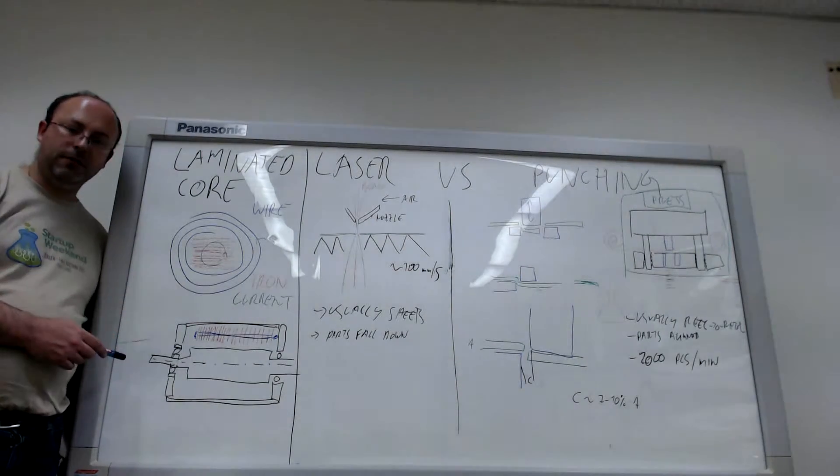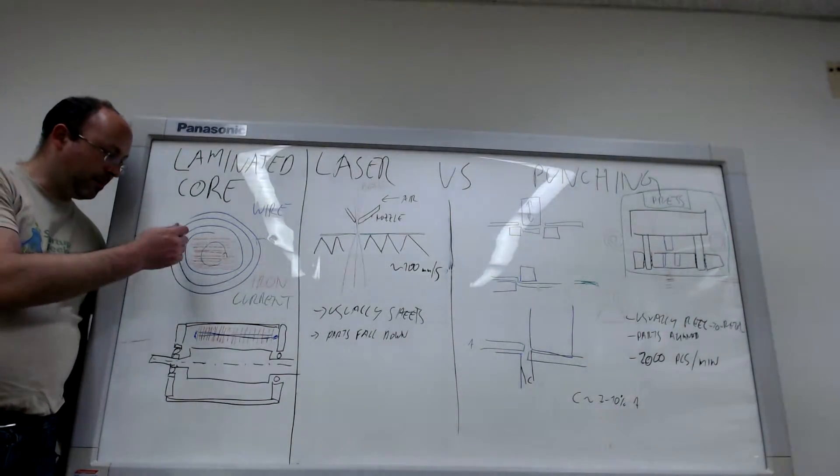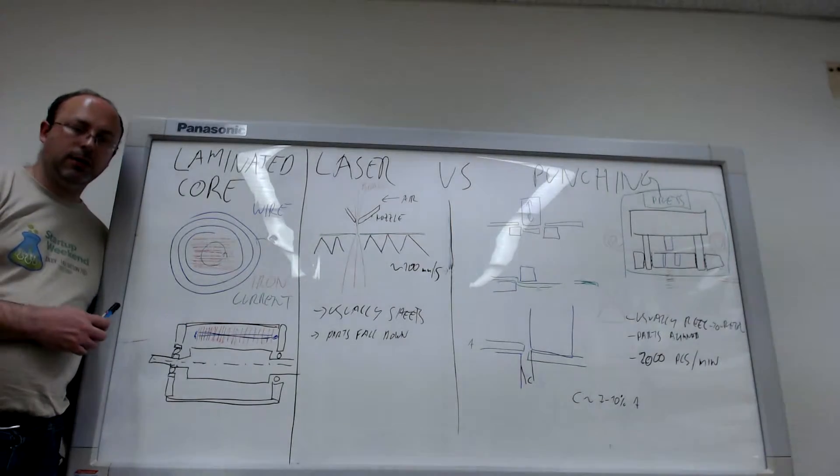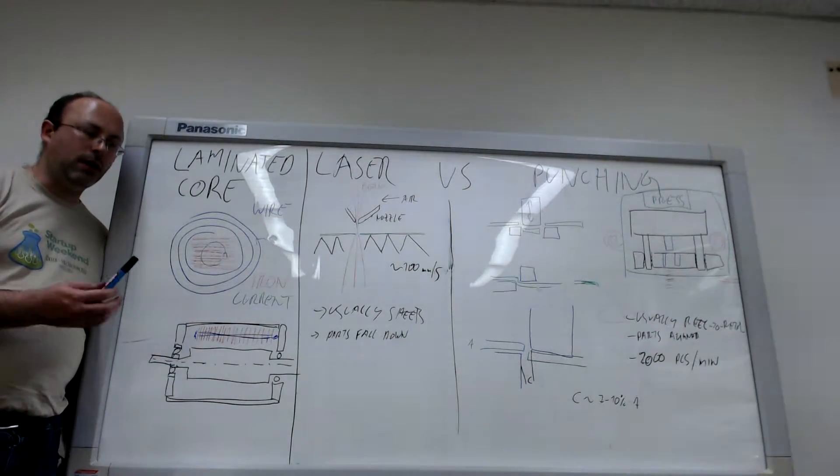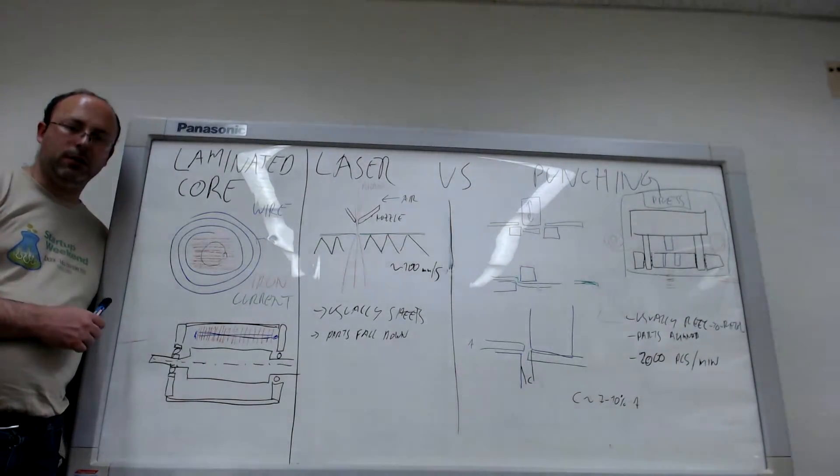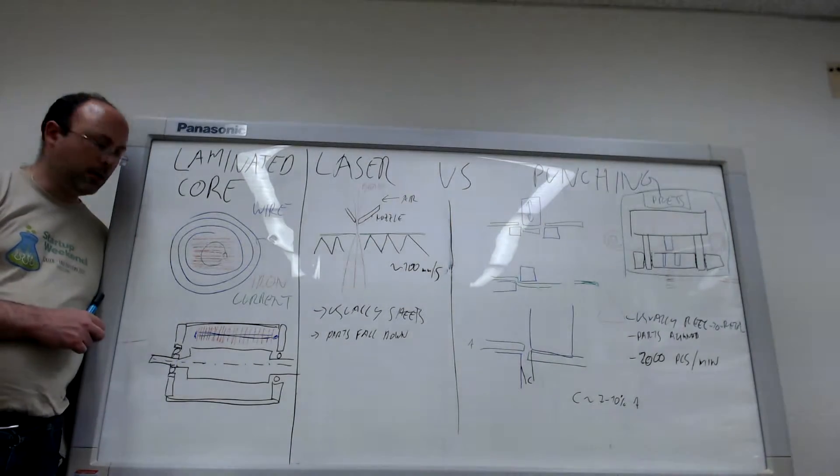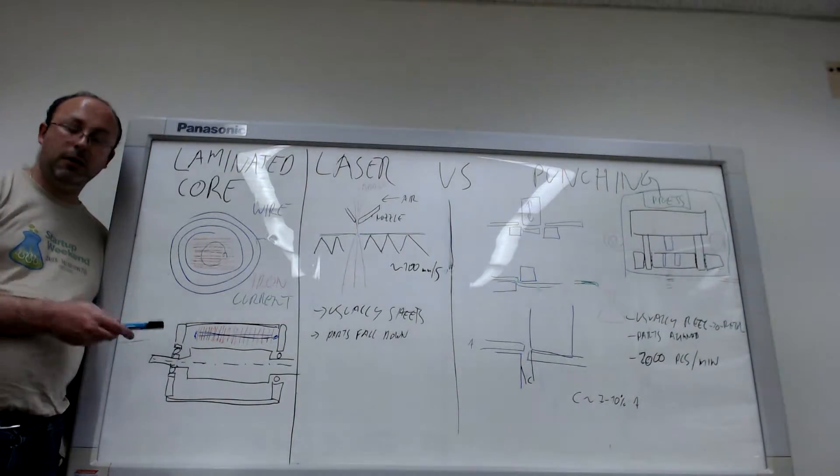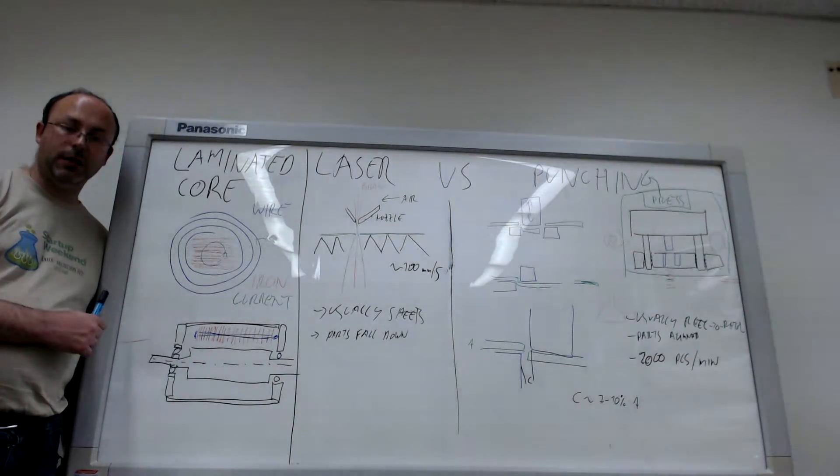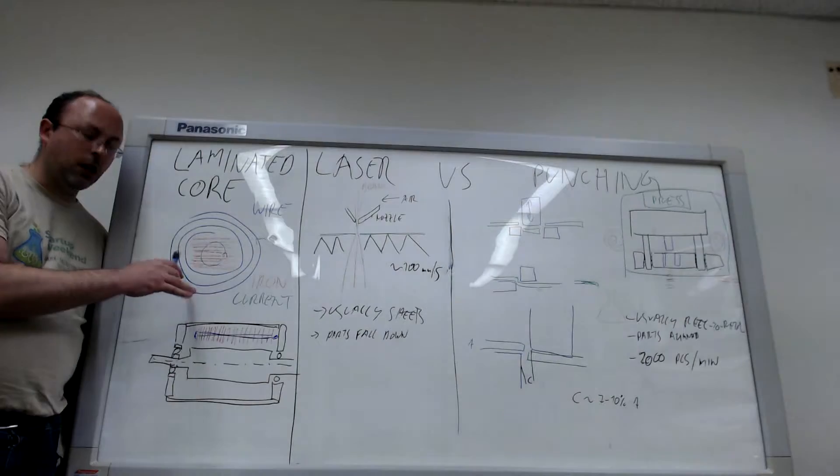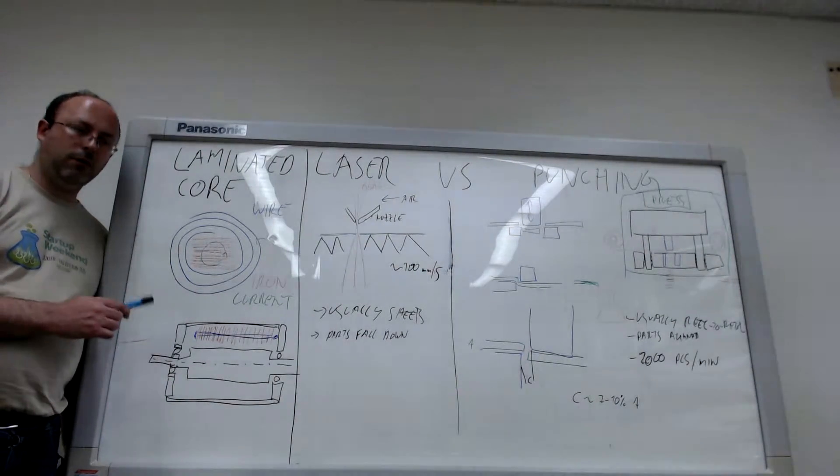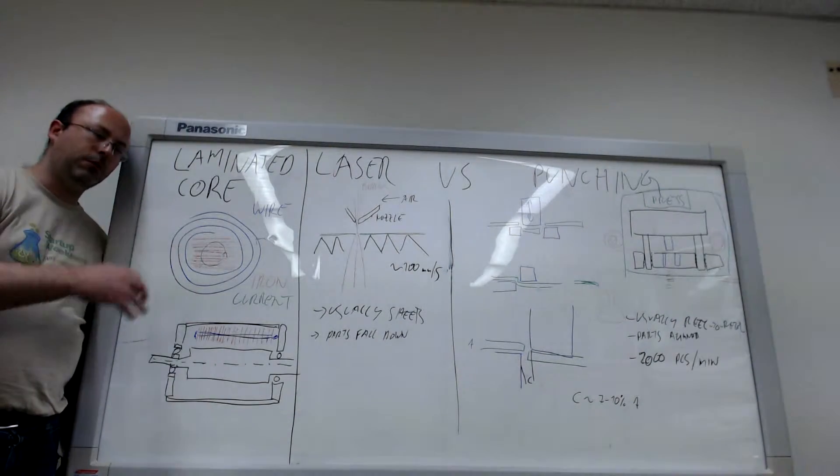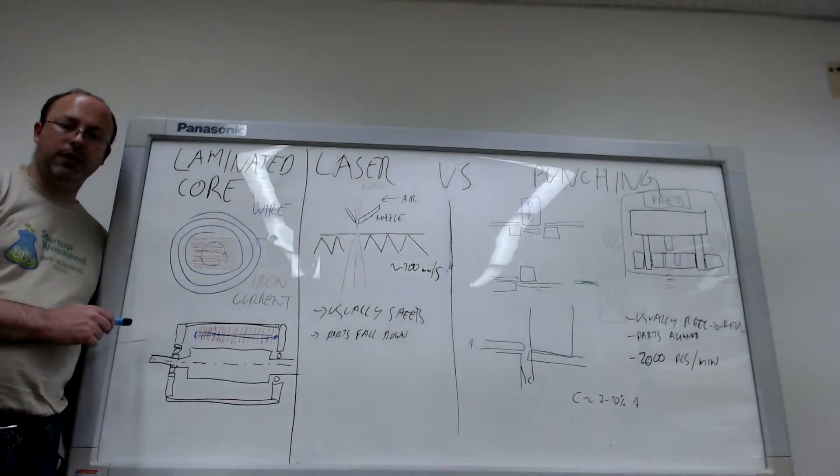Second important factor is also the exact material you use. There are many different qualities of electrical sheets and also the frequency you drive your motor because these eddy current losses become higher with higher frequency.